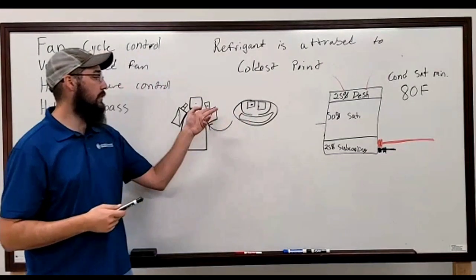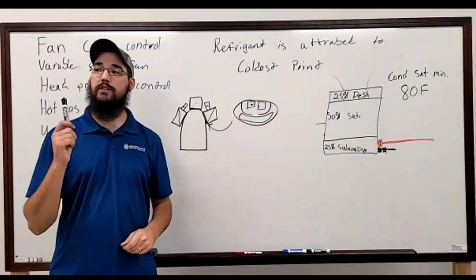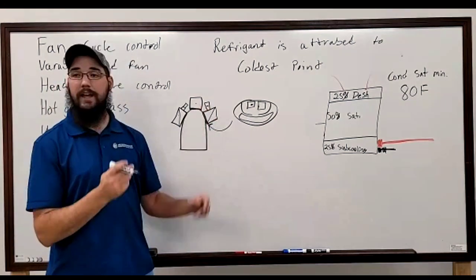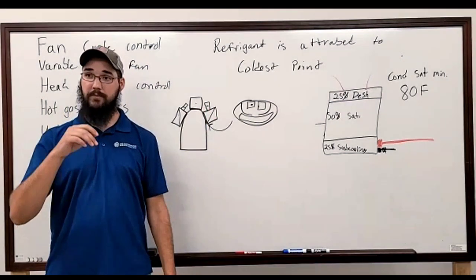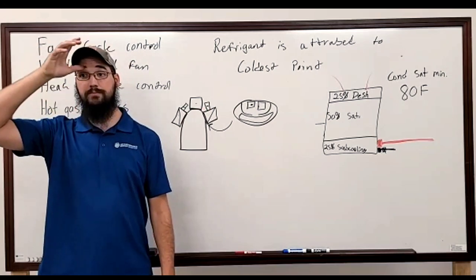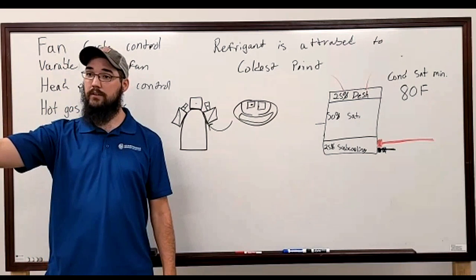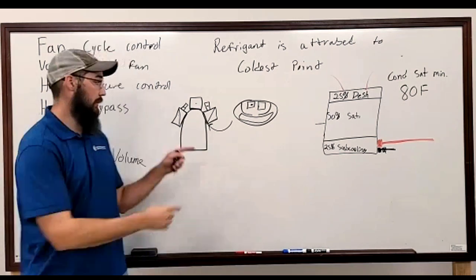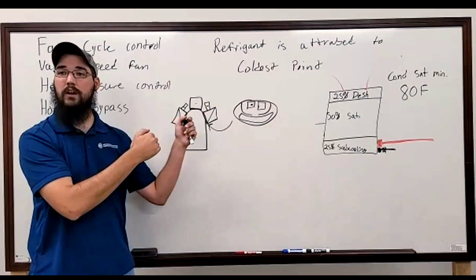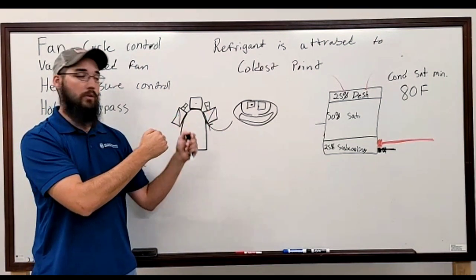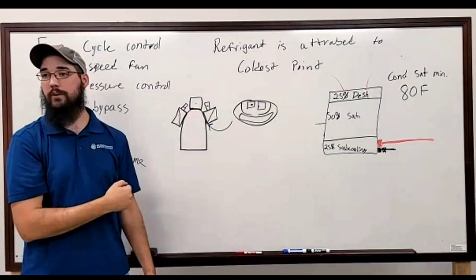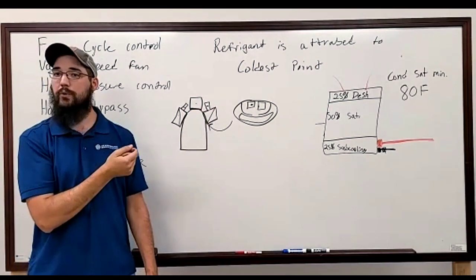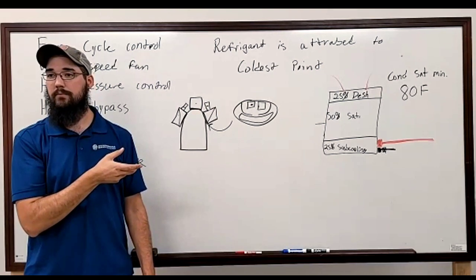What is it? Pressure. So specifically, there'll be a little pressure tap. It'll be monitoring the suction pressure. And when suction pressure drops to a certain pressure, which will be manually calibrated by you, they'll have a brass nut you can take a crescent wrench to and adjust. It'll have a cut-in point, a cut-out point. And depending on where the suction pressure lands, it'll cut in and cut out accordingly. And you'll set one slightly offset from the other. So this may be your first stage, this will be your second stage, loading and unloading. And then there's a little Allen wrench on the side, and you can take a cap off and adjust an Allen screw, and that'll adjust the DP between cut in and cut out.